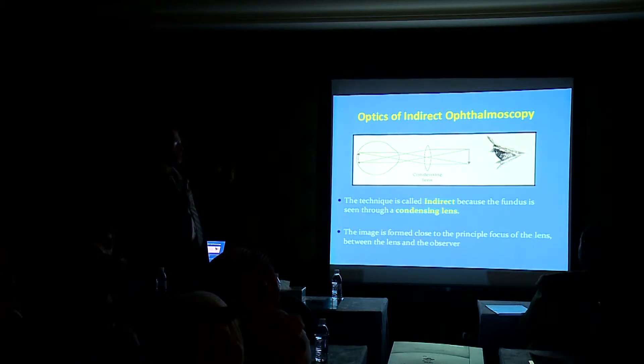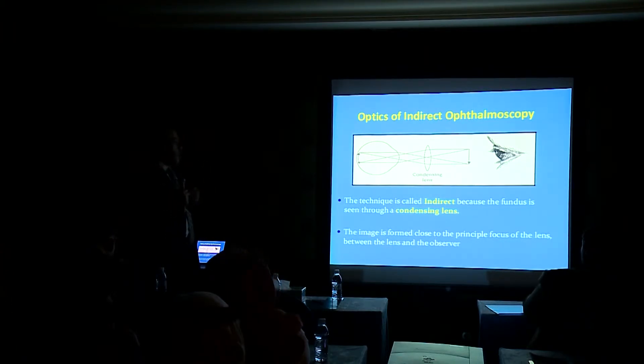The optics of the indirect ophthalmoscope depends on a condensing lens which projects light to the patient's eye, and the technique is called indirect because the fundus is really seen through a condensing lens. The image is formed close to the principal focus of the lens between the lens and the observer.